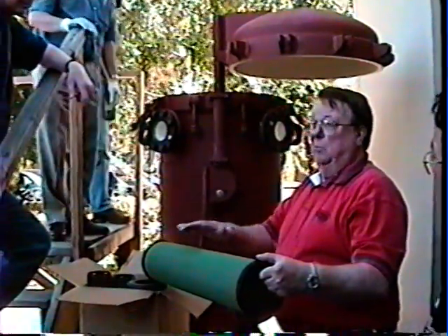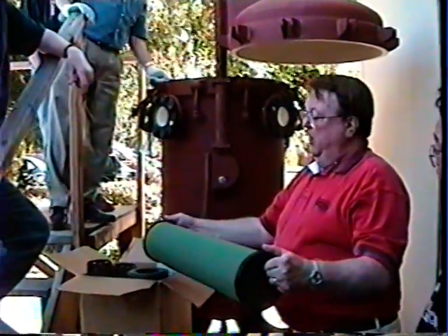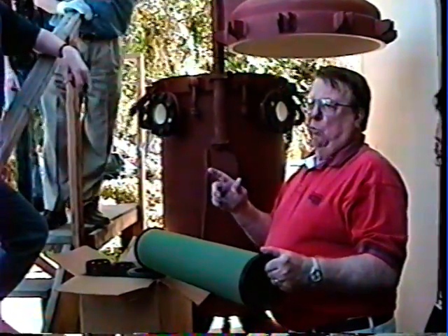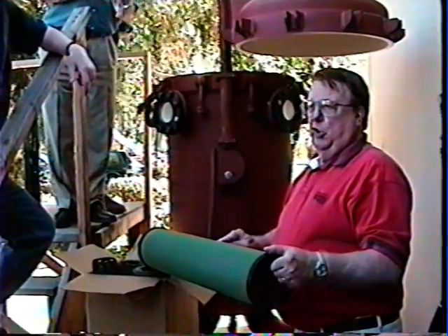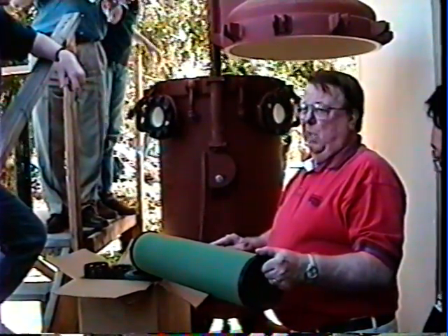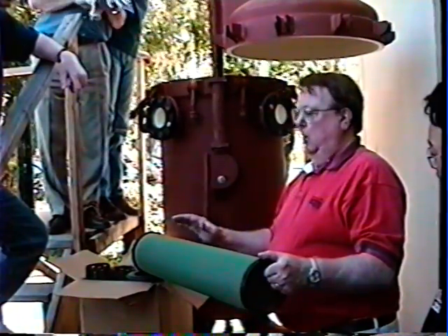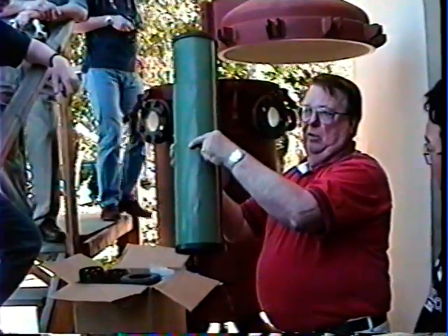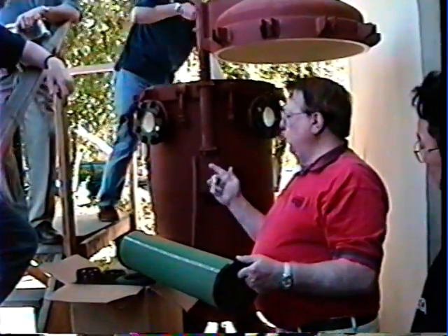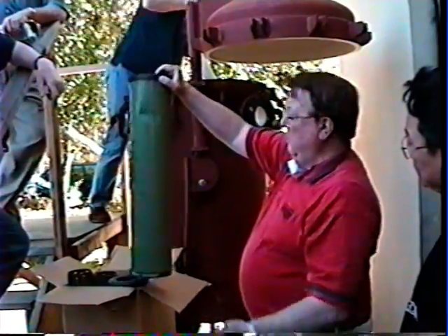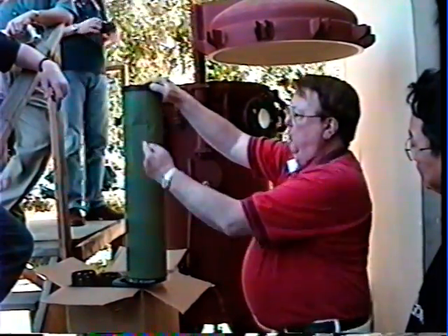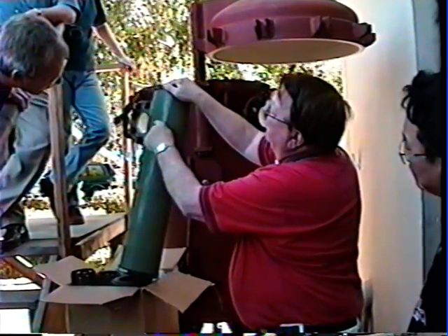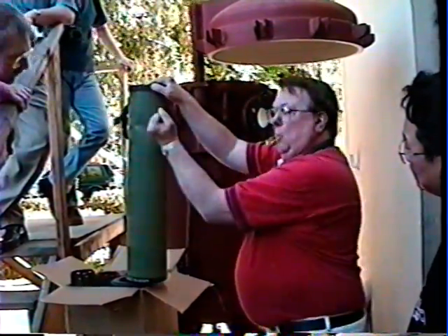Yes, you can clean them, but generally what will happen is they'll change the coalescers about 3 times, then they change the Teflon separators. Because most maintenance guys will not take care of them. They're always doing this, or somebody will hand it to them, they'll wrap them like this. So that's why we say always wear white gloves. If it's dented like that, do not put it in, because we don't know what happened to our Teflon. See our Teflon, there's a little light. So that could be like poking a hole with a screwdriver.